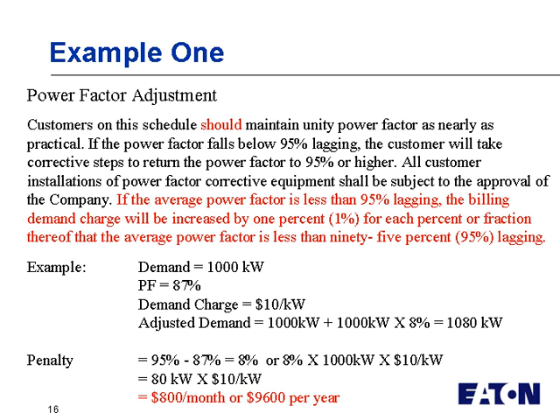And so, for example, if your demand was 1,000 kW and your actual power factor is 87% or 0.87, remember again, they say the power factor has to be greater than 95, so it's less than that. So they're going to increase your demand, and they're going to adjust it by 95 minus 87, which is 8%. So they take that 1,000 and multiply by 8%. And so you're paying 1,080 kW even though you're only using 1,000 kW.